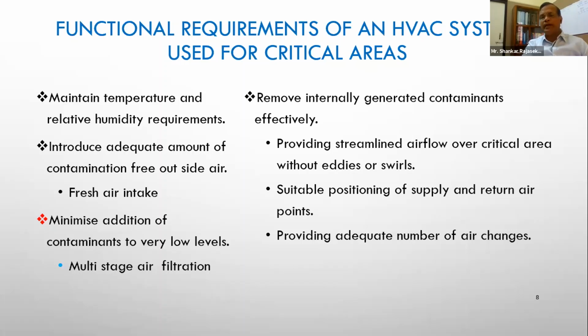Suitable positioning of supply and return air points. That's very, very important. If we keep it in such a way that the supply air, instead of coming into the room, gets bypassed and a part of it goes directly into the return air point, then it's not done its job. We have not taken the benefit out of that. So we'll have to look at the positioning and look at the adequate number of air changes. How many air changes to provide? So these are all the functional requirements of an HVAC system used in a critical area, and each one of them has to be taken care of.